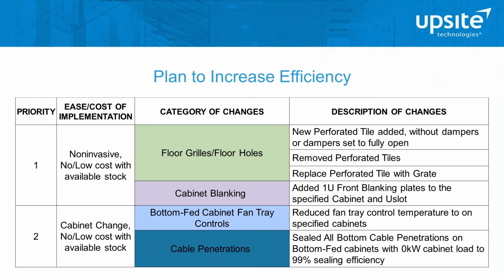For number 2, some of the cabinets had fan trays that were temperature controlled. We had to optimize individual fan trays and set new temperature controls in order to optimize the airflow through the cabinets, as well as the effects they have on neighboring cabinets. These were all done following full calibration of the data center and running simulations for different scenarios.